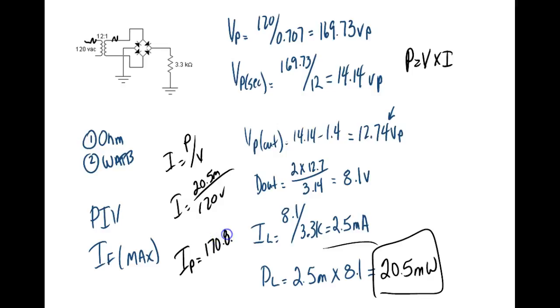170.8 microamps. So look, if I was to put a fuse over here, if I was to raise this up to 150% and put that in the primary, that transformer would burn up, right? You understand that the fuse would. And that's the big problem we have - people overfusing. They'll know what's in the secondary side, and then they'll fuse the primary side for that same amount.